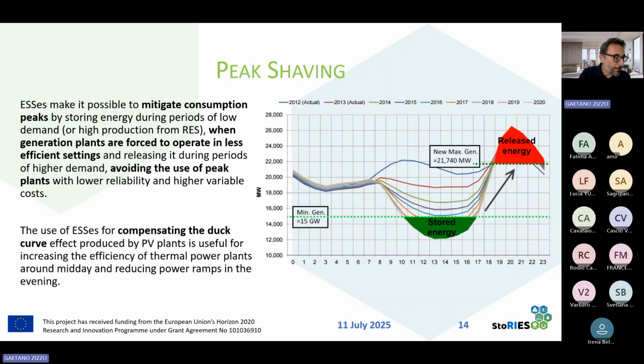The second application is peak shaving. In this case, batteries make it possible to mitigate consumption peaks by storing energy during periods of low demand or high production from renewables, when generation plants are forced to operate in less efficient settings. And then storage systems are used for releasing the stored energy during periods of higher demand, in this way avoiding the use of peak plants that have lower reliability and higher variable costs.